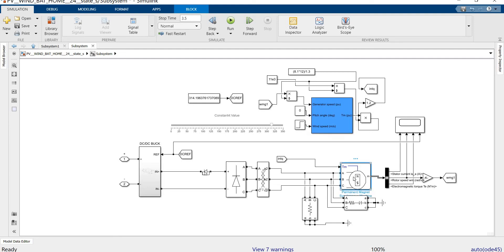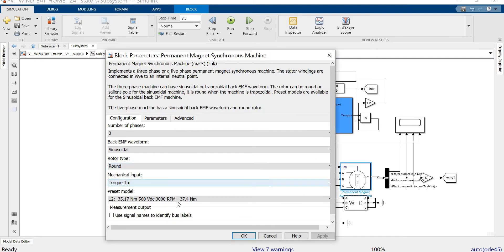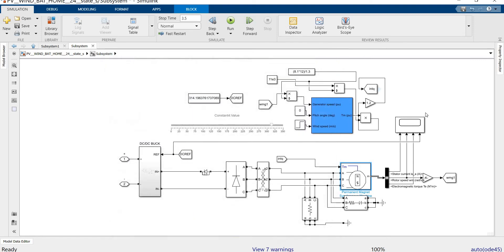This is an 11 kilowatt system. We have chosen a permanent magnet synchronous generator (PMSG) rated at 37 Newton-meters, 560 V DC, and 3000 RPM full speed. The output of the PMSG is connected to an isolation transformer.